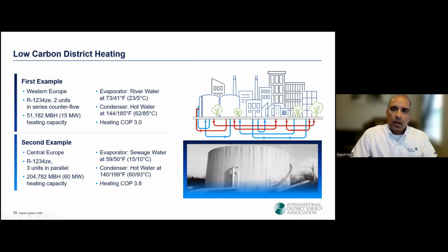So similar to our previous modes that we explained, let's discuss 2 examples that are great examples of low carbon district heating. Once again, we are not producing any chill water for beneficial cooling. So we are feeding the evaporator with something that is other than chill water. The first example is in Western Europe, where the heat pumps are delivering as high as 185 F or 85 Celsius hot water for district heating.